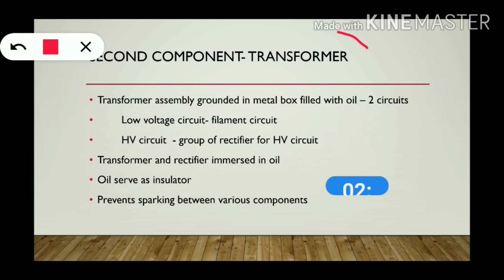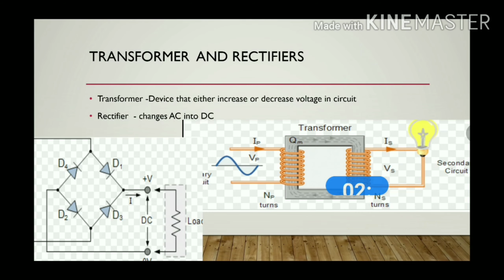The second component जो है main, that is the transformer. The transformer assembly is enclosed in a metal box that is filled with oil and has 2 circuits. The low voltage circuit, that is called the filament circuit, and the high voltage circuit, there is a group of rectifiers for the high voltage circuit. The transformer and rectifiers are immersed in oil, and the oil serves as an insulator. So it prevents sparking between the various components.